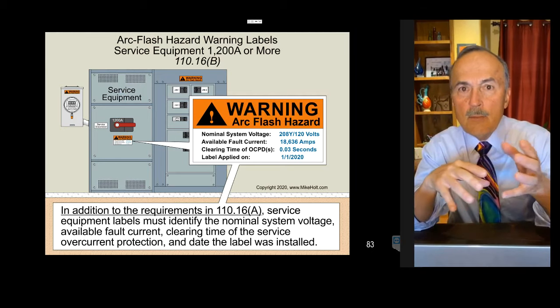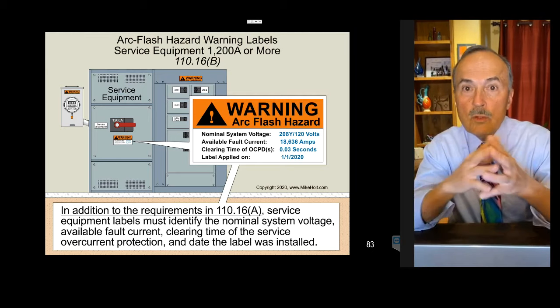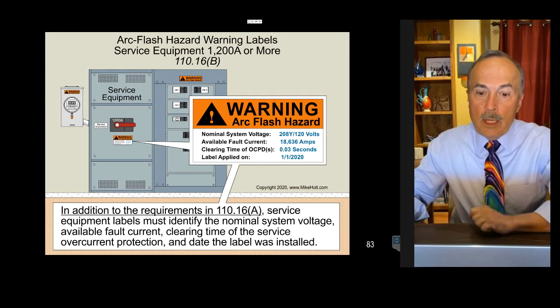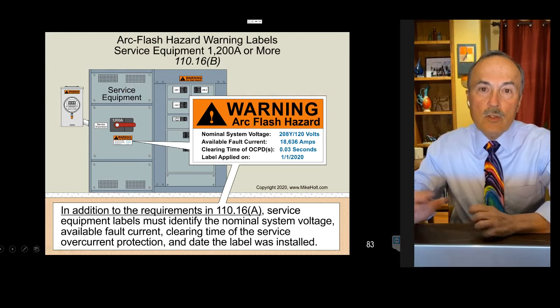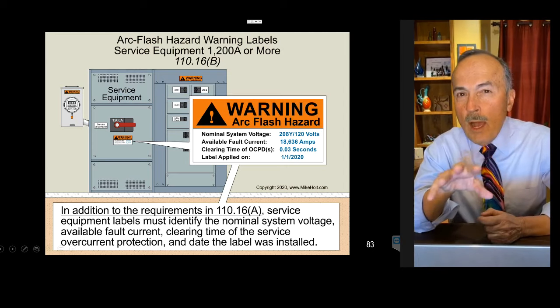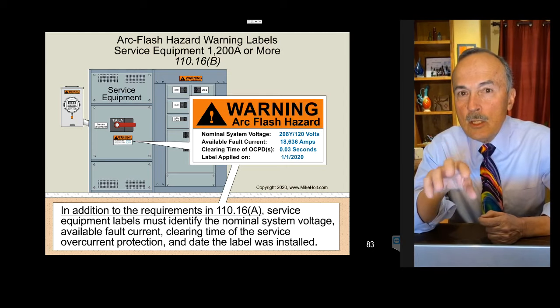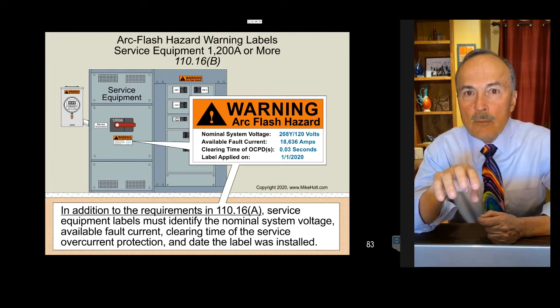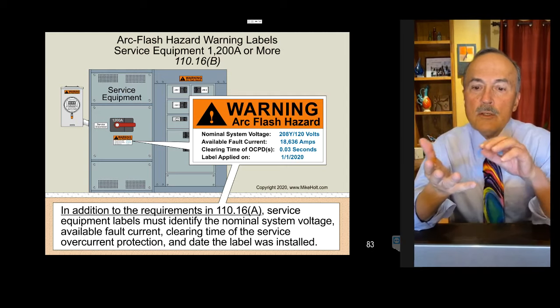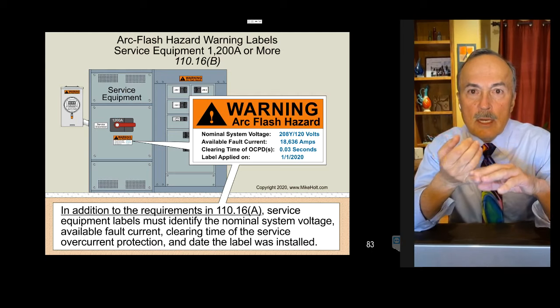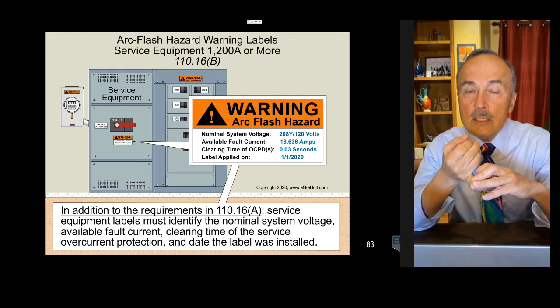You should know where to get the software to figure out the fault current calculation. You should know about getting the utility, doing the math, and you really need to take like a class in this type of material. We cover this in my seminars, of course. We cover this because it's a code rule. So going a little further, then if you have this is going to be a circuit breaker with a clearing time. And you know why they want that information?